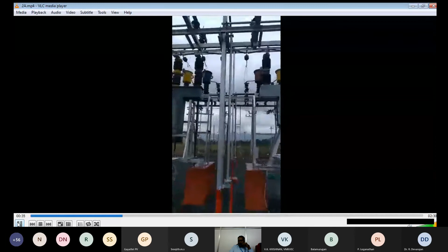And there will be a CT also on the back side. You can see the current transformer. This current transformer is used for both protection and metering, to measure how much current is available for metering purposes as well as for protection. The secondary 2 core will be available in the current transformers, and it is used for both metering and protection.